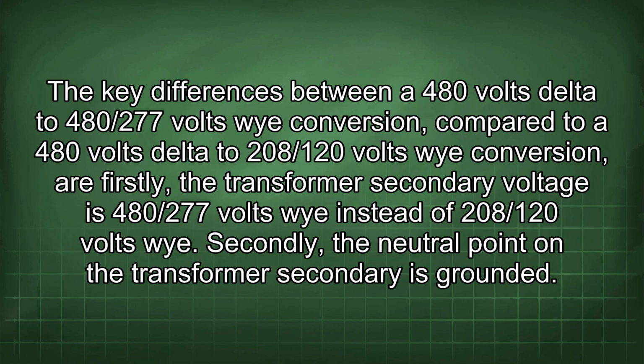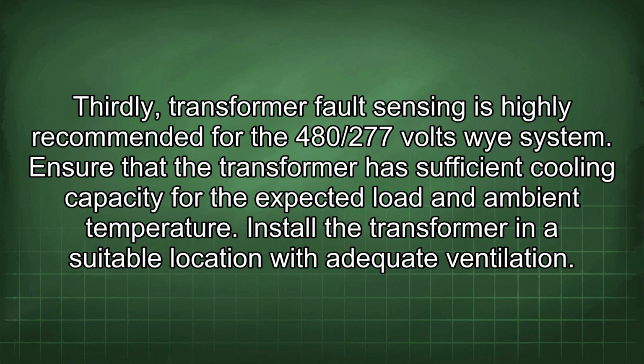The key differences between a 480 volts delta to 480/277 volts Y conversion compared to a 480 volts delta to 208/120 volts Y conversion are: firstly, the transformer secondary voltage is 480/277 volts Y instead of 208/120 volts Y. Secondly, the neutral point on the transformer secondary is grounded. Thirdly, transformer fault sensing is highly recommended for the 480/277 volts Y system. Ensure that the transformer has sufficient cooling capacity for the expected load and ambient temperature.